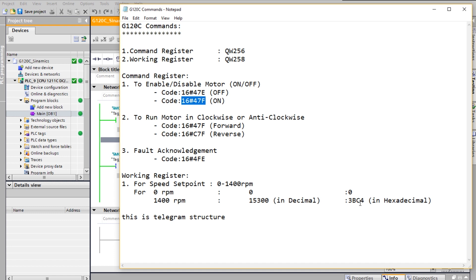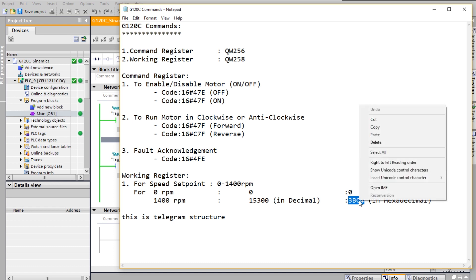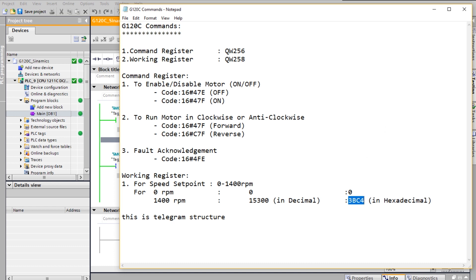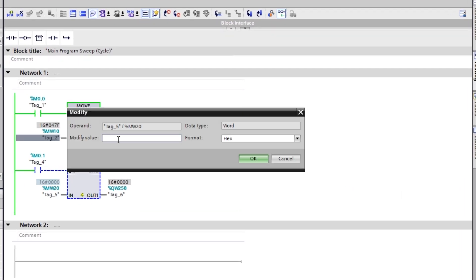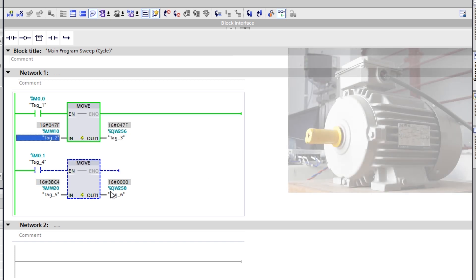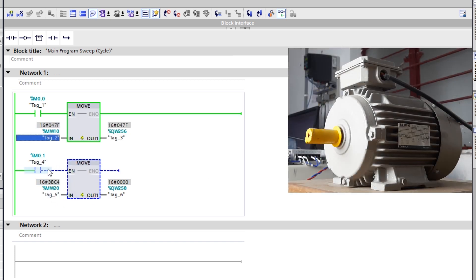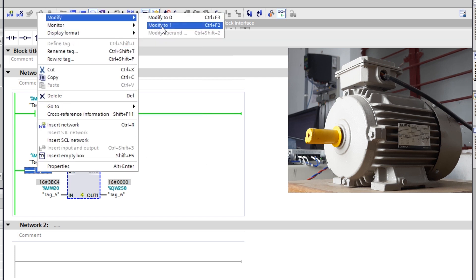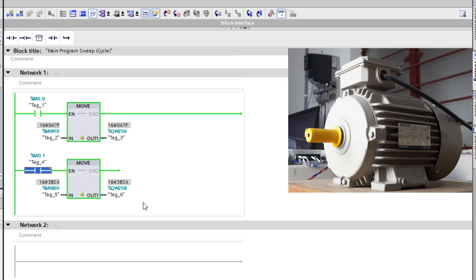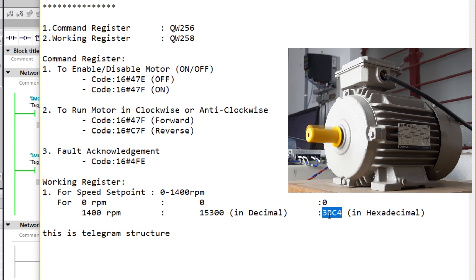I'm going to select the speed. As you can see, this represents RPM, and I'm selecting the maximum speed in hexadecimal code. I'm copying the same into register MW20. The moment I select M0.1 as high and toggle it to 1, you can see the motor has started at maximum speed — 1400 RPM in the clockwise direction. On the left you can see the motor is initiated at maximum speed.